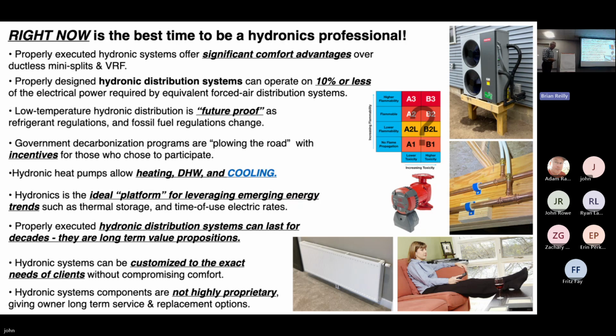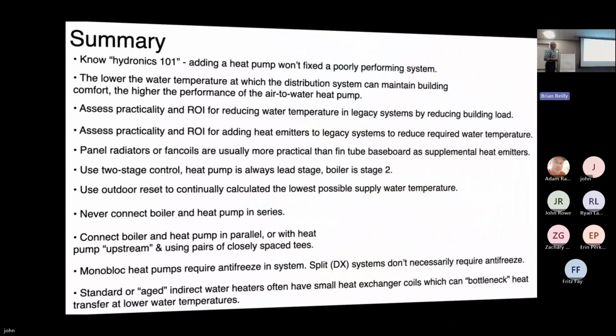The hydronics market has always been a small percentage of the overall, especially residential HVAC market. I blame that on Willis Carrier. Ever hear that guy? Yeah. Prior to Willis Carrier, most of the houses were heated with very old but functional hydronic systems, either steam or what we call gravity hot water systems, no circulators. Circulators didn't come into the market until the mid-30s. Prior to that, it was just buoyancy that moved the water through the system. And there's some beautifully engineered systems, no circulators at all. But again, I'll let you read that later.